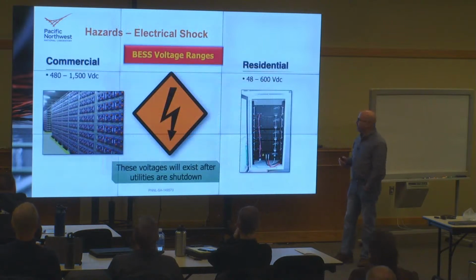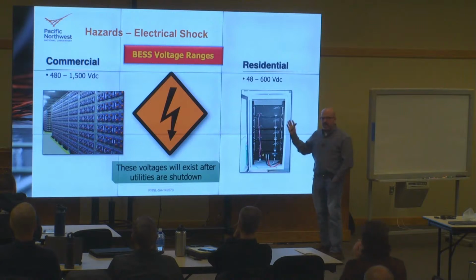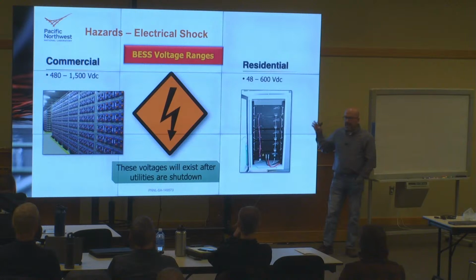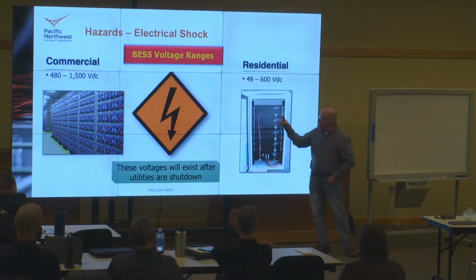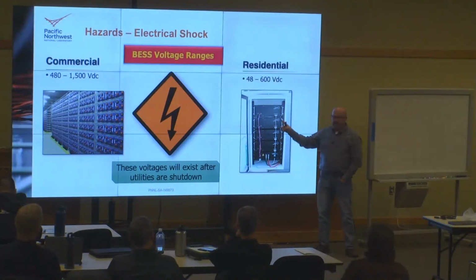Let's talk a little bit about voltage. On the residential side, batteries are typically between 48 volts and about 600 volts. If you approach a scene and see open bus bars — nothing, no plexiglass or metal covering them — that's less than 50 volts, because that's the OSHA threshold for touch-safe. If anyone's been in a telecom basement full of lead acid, NiCad, and iron batteries, those are all at 48 volts — you can touch those.